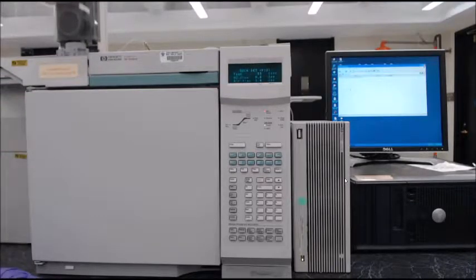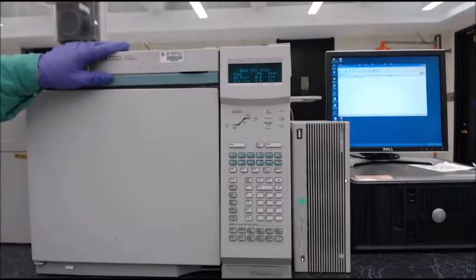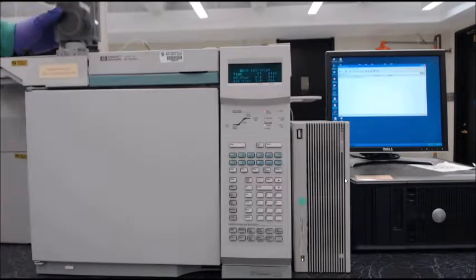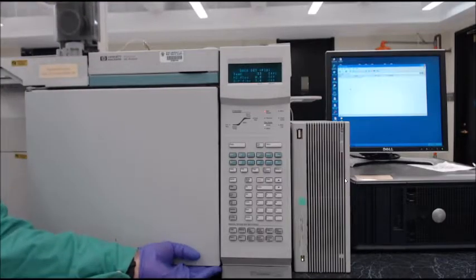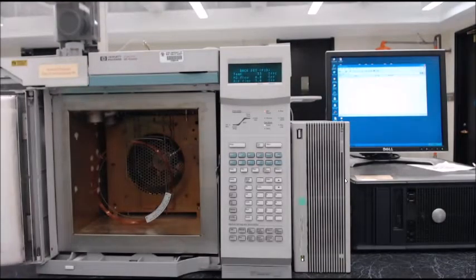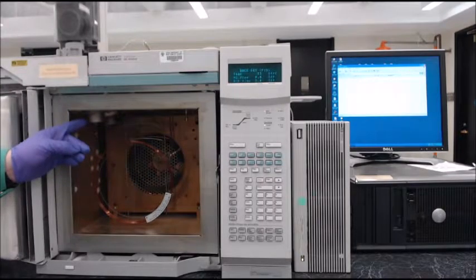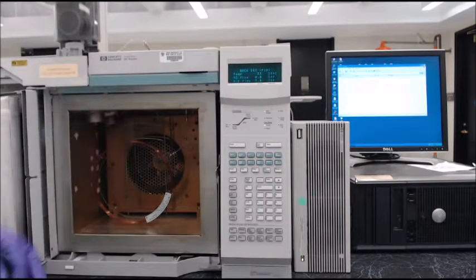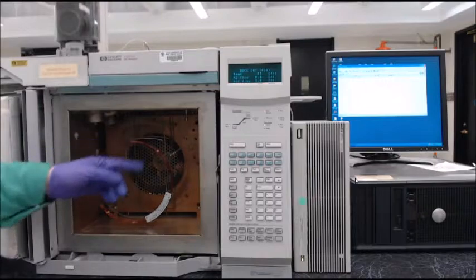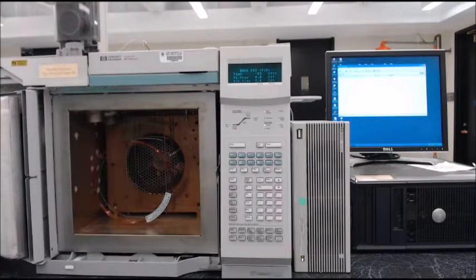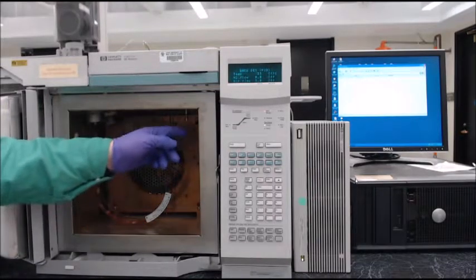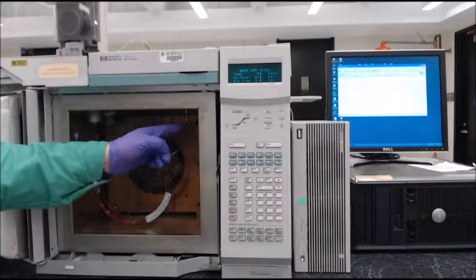In this video, I'm going to cover the gas chromatograph. The basic parts are the auto sampler, which draws sample from the sample tray and injects it via this injection port. Generally speaking, this will be quite hot. The sample goes into the column, which sits in the oven. It is separated in the column and fed into the detector.